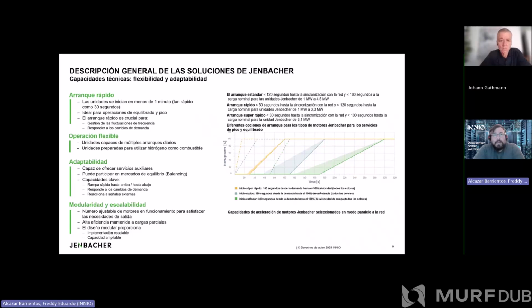Then there's high efficiency that is maintained at partial loads. What does that mean? Remember that for engines, the highest efficiency is found when we are at maximum power. If a plant has, say, 100 megawatts, a 50 megawatt partial load can be met by units running at 100%. This means the plant is at 50% capacity, but the units themselves are not. Therefore, there is lower gas consumption and higher efficiency. And once again, the modular design enables scalable implementation and expandable capacity. These are truly very important things that must be taken into account.